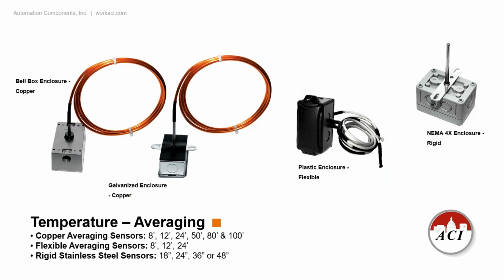We also get involved with averaging. A lot of people don't know this, but we can actually make averaging sensors all the way up to 100 feet in length. Now our standard lengths are 8, 12, and 24 foot, but for copper thermistor averaging, we can do up to 50 foot, and platinum RTD averaging, we can go all the way up to 100 feet in length. We do also manufacture flexible averaging, as shown there on the right side, and that is standard lengths of 8, 12, and 24 feet.